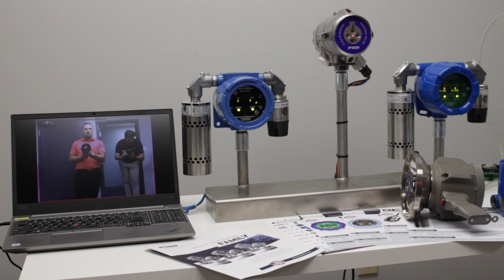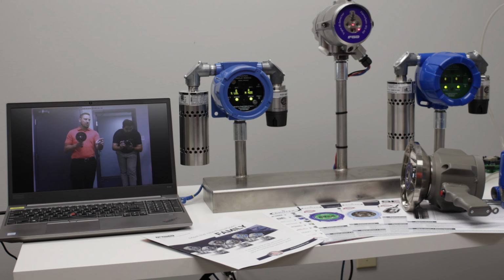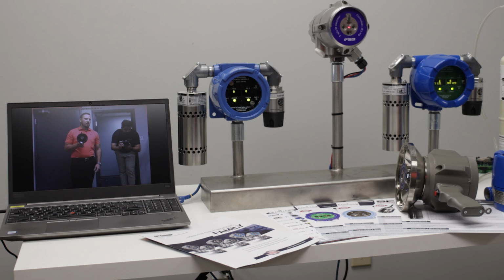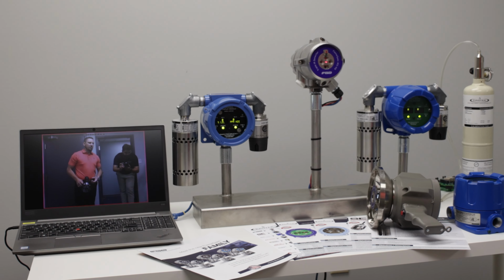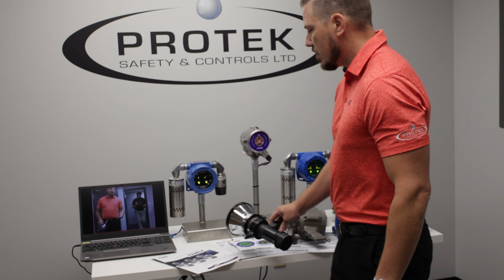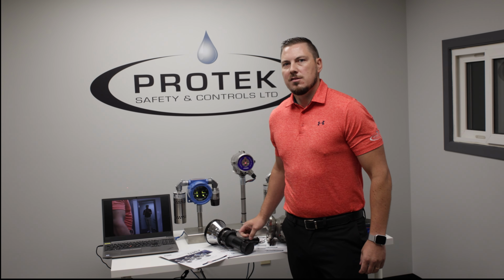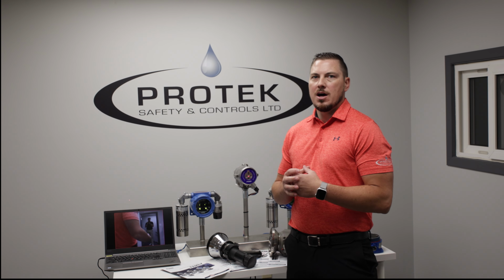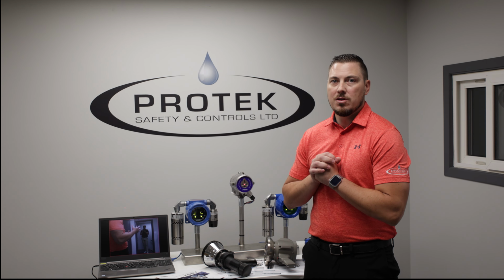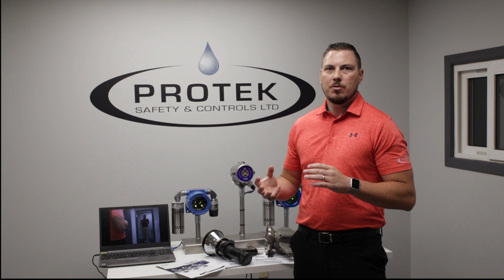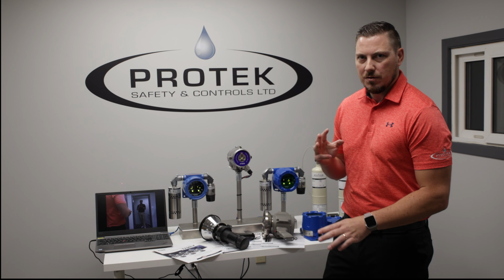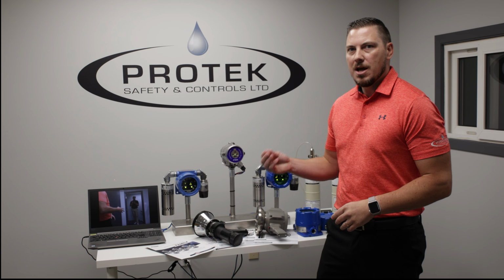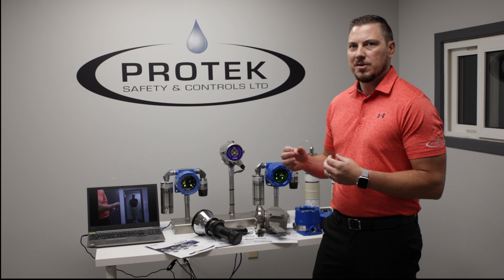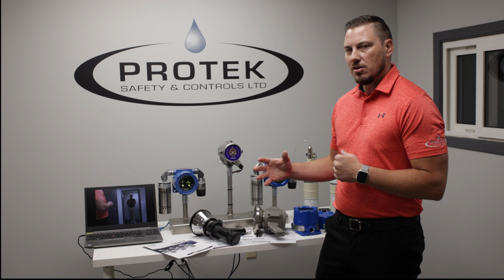There we are. You'll see the screen goes red, it detects it, and now we're good. We know it's going to respond. So we're actually exercising the sensors. The difference between UVIR and IIIR technologies is the amount of sensors that we're utilizing from a high-level false alarm immunity perspective. With a IIIR, we have 3 infrared sensors looking at 3 different spectrums of the energy bandwidth, looking for a signature specific to flame to give us that signal output.